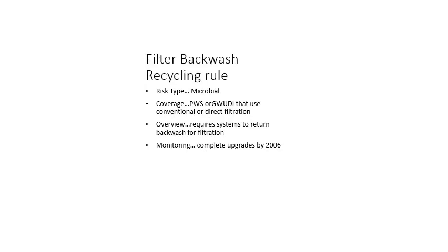Filter backwash recycling rule. The risk type is microbial. Coverage is public water systems or groundwater under direct influence that use conventional or direct filtration. The overview: it requires a system to return backwash through filtration. Upgrades had to be completed by 2006.